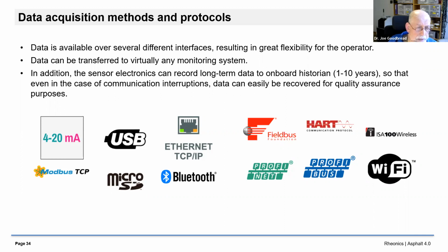And a side effect of flexible data interfaces is the possibility of onboard data logging and archiving, making sure the data is usable and available, even if the data flow from the sensor to the central automation system is interrupted. The sensor electronics has a little SD card in there, and even if all else fails, you can pull the data off that card.